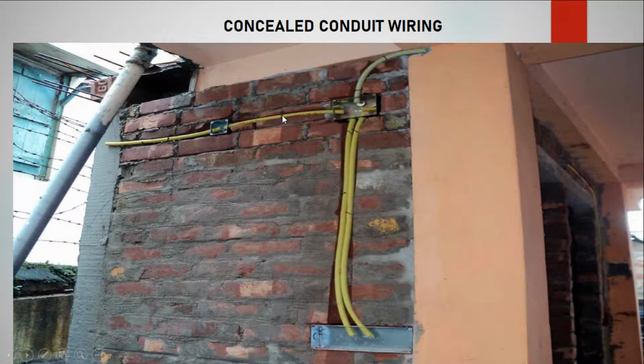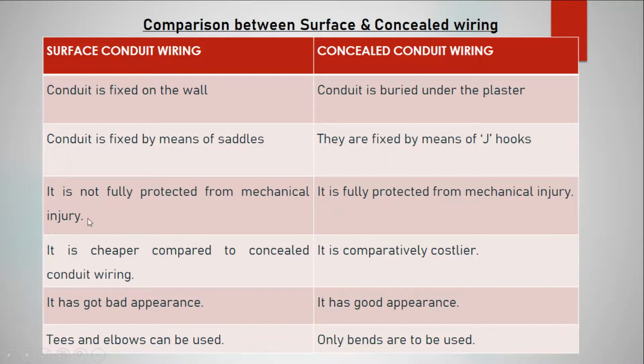J hooks can be used for the concealed type of wiring to fix it on the walls. Some J hooks here and there are what you use. Surface wiring is not fully protected from mechanical injury because it is quite open. But concealed conduit wiring is fully protected from mechanical injury. Surface conduit wiring is cheaper compared to concealed. Concealed wiring is very costly.